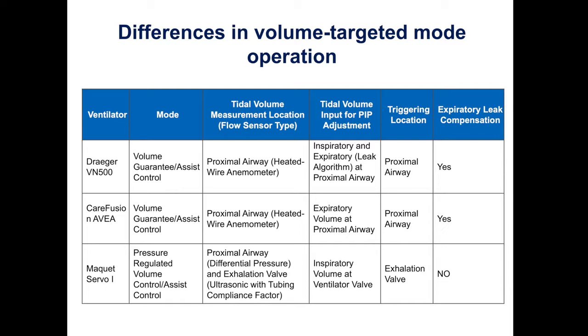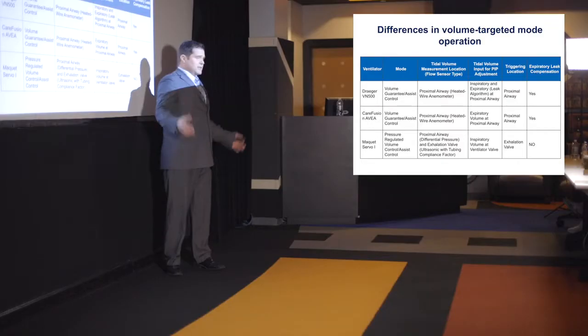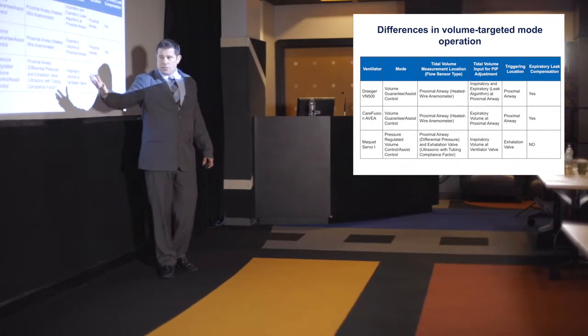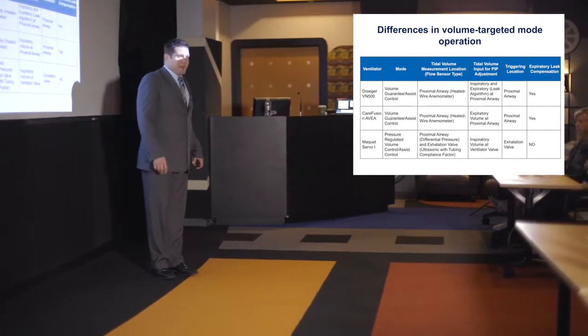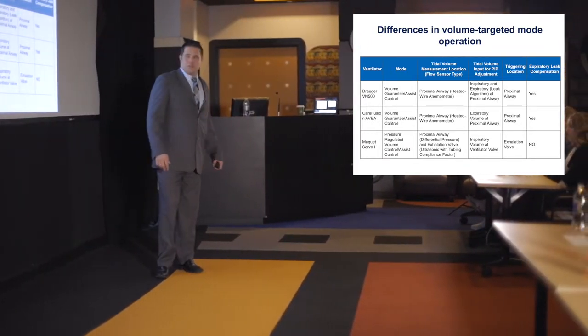This one has a leak compensation algorithm which, upon exhalation, preserves the PEEP when it's activated, but it also adds additional flow to make sure that you're able to trigger effectively. So there is less likelihood of auto-cycling the ventilator. And with the Maquet Servo I, widely used in the NICU, I see it all over the place. And I actually was a huge Servo supporter with the 300 for years. I thought that was a wonderful little ventilator.